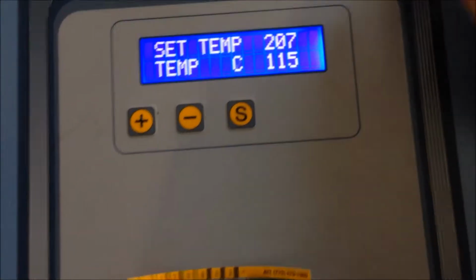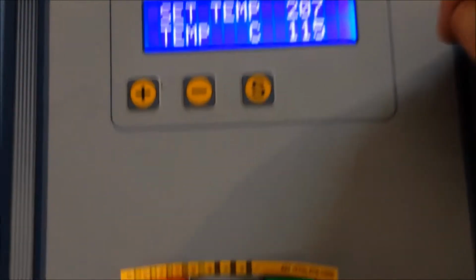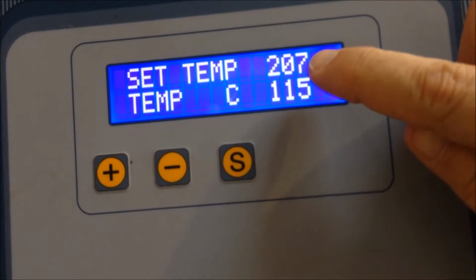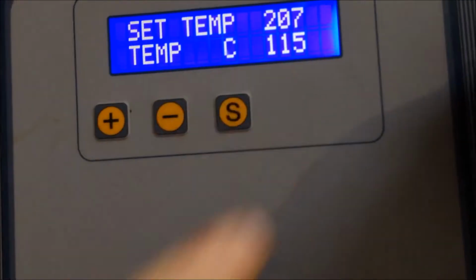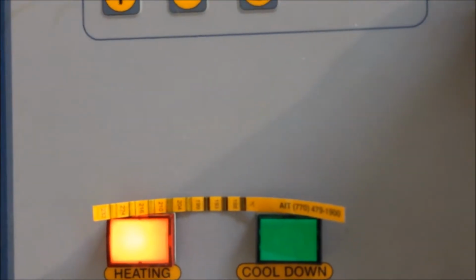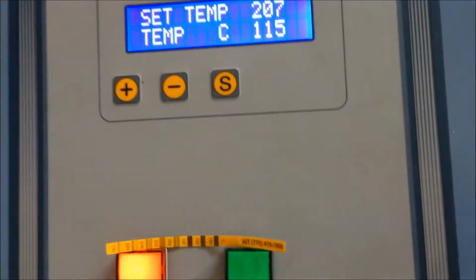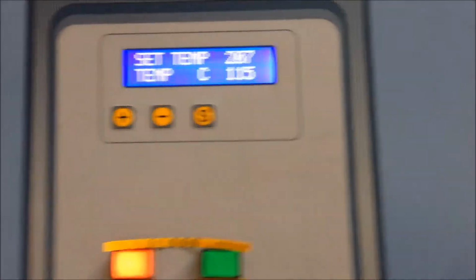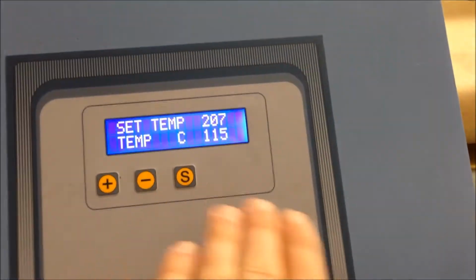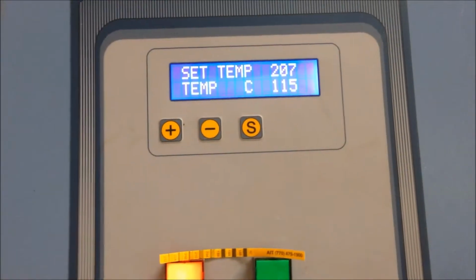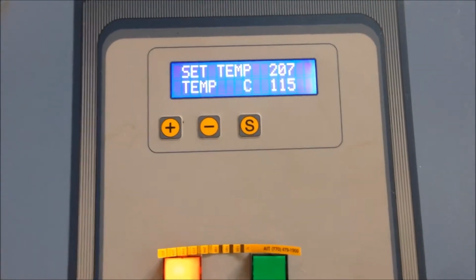So what they should do is they should set this to exactly what this temp strip is. Yes, that's what the goal is, to get this number and your temp strip to read exactly the same. Okay. And how do you get there? Do you just make the adjustment carte blanche here on the lower set point?